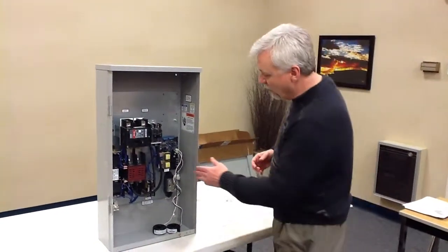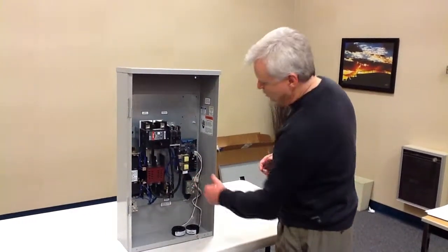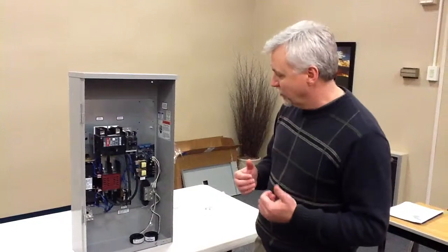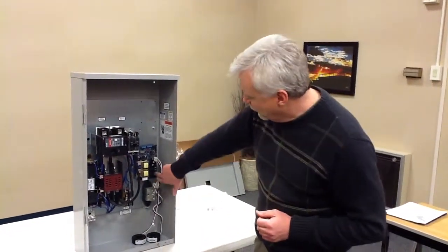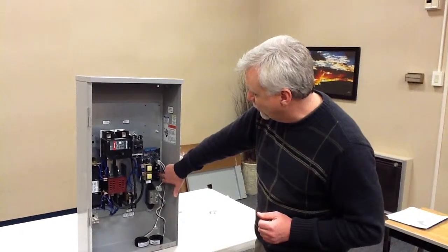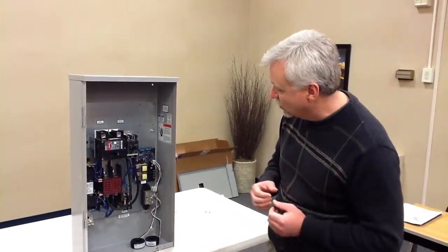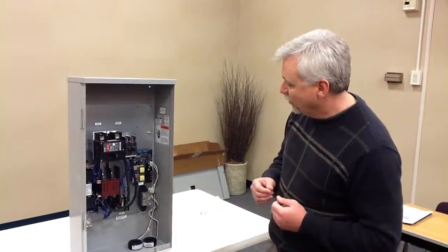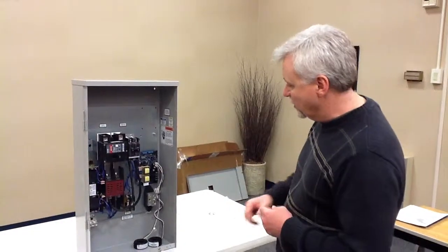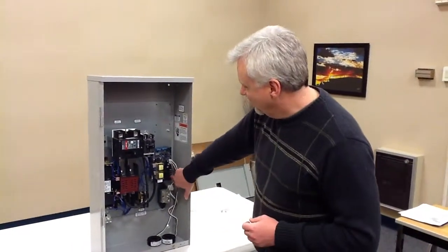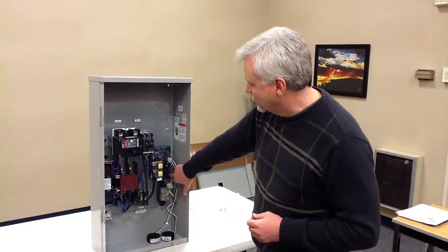And then the C component is anything that you want to have under the managed portion of the generator that can be reduced from the calculated load and downsize the generator. Those are going to fall under these two termination points here on what we call the ACCM, or Air Conditioner Control Module. You'll simply take the thermostat wire that's running to the air conditioner's condensing unit, and you will bring it into this transfer switch and load it on the A terminals here.